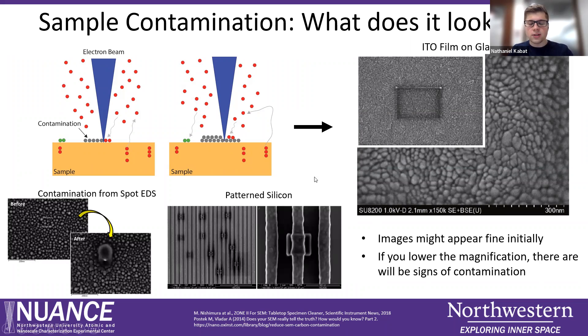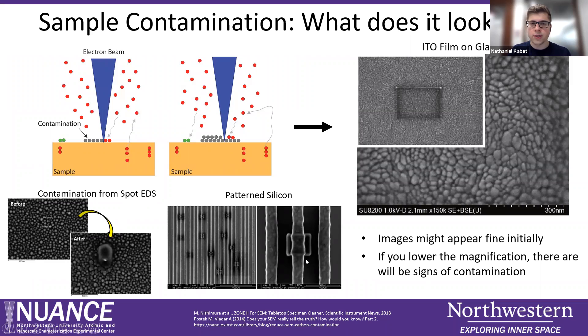What does this actually look like in terms of an SEM image? On the right-hand side, you can see an SEM image of an indium tin oxide film on glass. The larger image itself may look okay initially, but if you lower the magnification a little bit, you can see artifacts that were not there prior to scanning — they come from the buildup of sample contamination. You have a thicker bar at the top due to the scan direction and some blackened features in the region. If you lower the magnification and see strange features, that's a sure sign of sample contamination. Other examples include buildup from energy dispersive spectroscopy when you dwell the SEM in one spot for a very long time, as well as carbon contamination buildup from a patterned silicon sample where the buildup visibly broadens features — which can be a problem if you are trying to quantify the line width of a small feature.